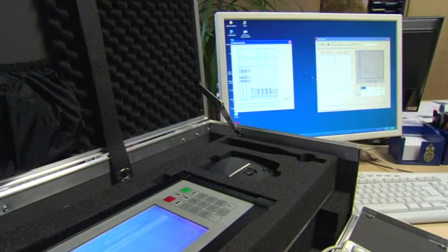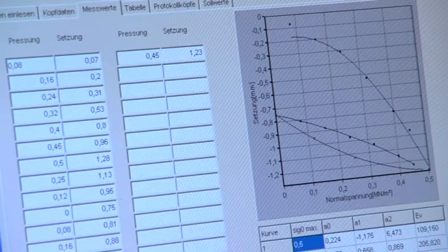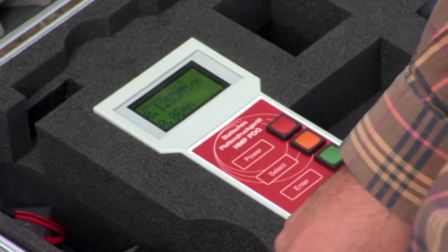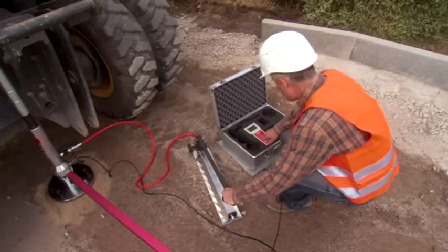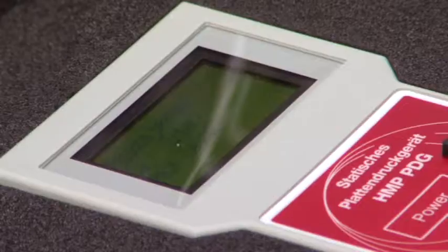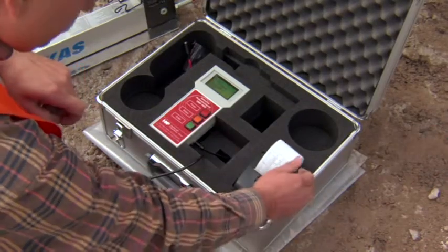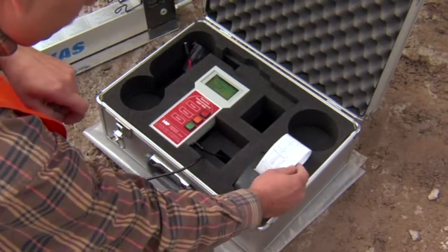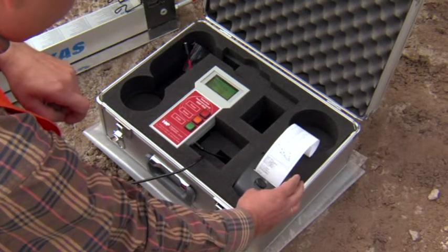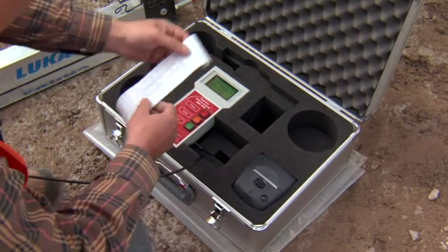There are a number of evaluation units for this machine. The electronic evaluation units HMP PDG-SD and HMP PDG-D are easily affordable and compact. They allow for automatic data transfer, calculation, display, and printout on-site. With a built-in powerful battery, the devices can run for up to 12 hours. The thermal printer enables you to print out the data and pressure settling lines directly on the construction site.